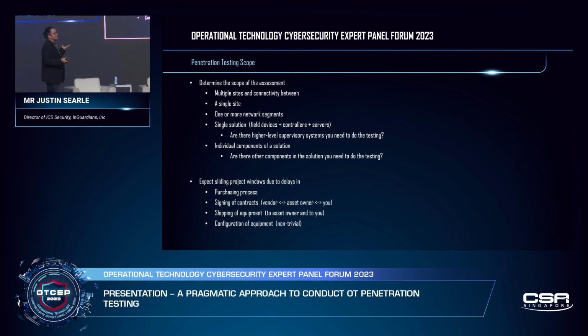We just had a client over the last couple of weeks with a component that we clarified and validated 3 or 4 times in a row had been initialized and connected to a system before they shipped it to us. And when we received it, it had not been initialized. So make sure that you actually get that last one done.